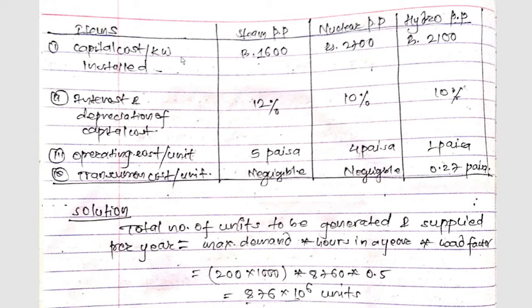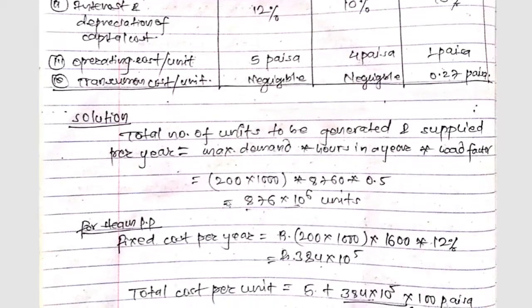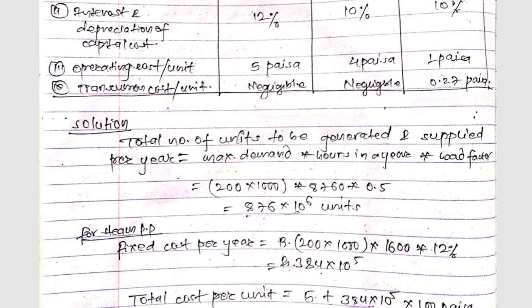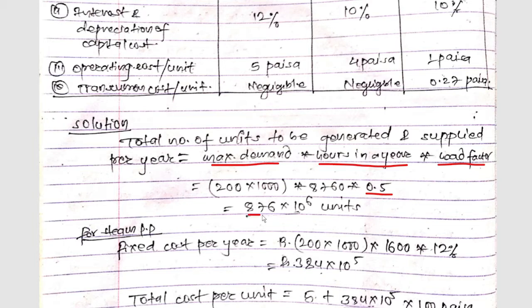The data given includes capital cost per kilowatt installed for steam, nuclear, and hydro power plants, along with interest and depreciation of capital cost and operating cost for each. First, we calculate the total number of units to be generated and supplied per year: maximum demand × hours in a year × load factor = 200 megawatt × 1000 × 8760 × 0.5 = 876×10⁶ units per year.